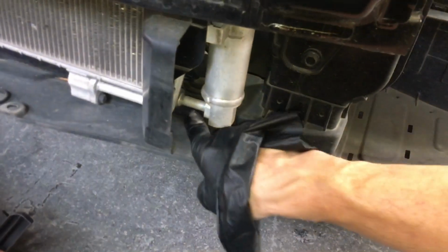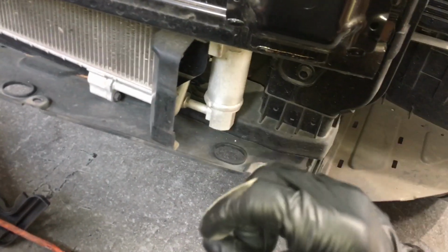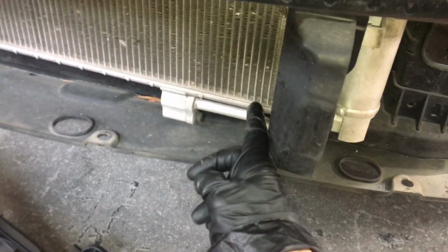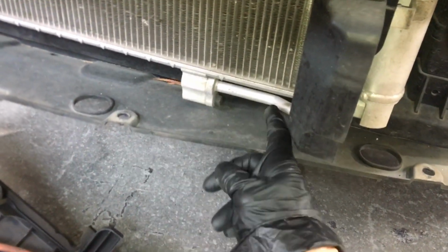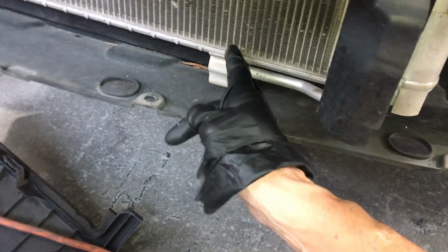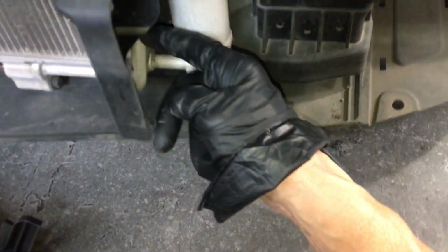Here's our receiver dryer, and as you see, the lines going in and out of the receiver dryer are exactly the same size. You don't have a slightly bigger one and a smaller one coming out. Look at the lines - you have one going right into the heat exchanger, and another one going into the same tube header coming off the dryer here, all on the same tube header.